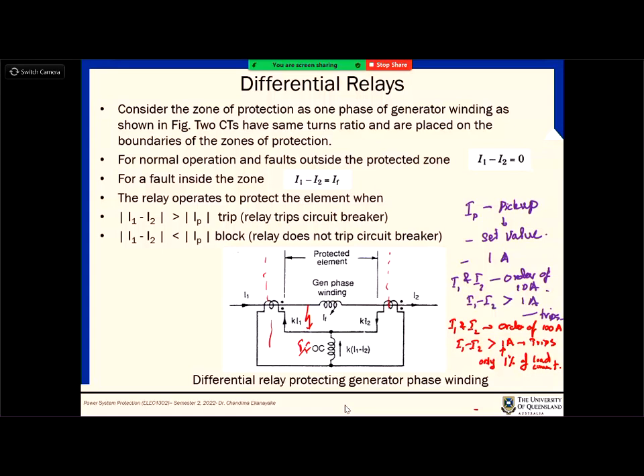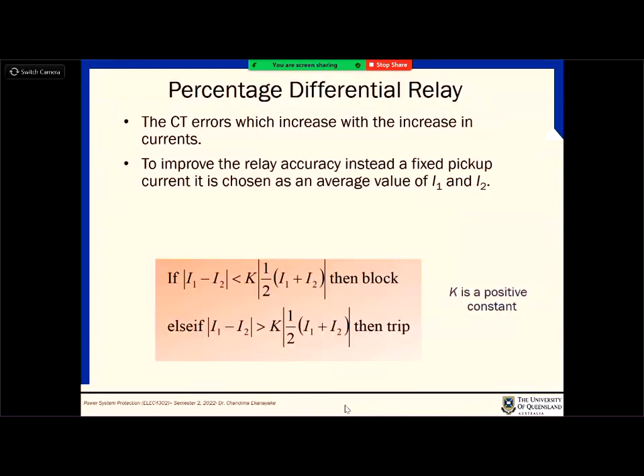As an example, absolute pickup means you take a relay and tell it to operate when, let's say, the differential current is 1 amp, which is the absolute value. So to overcome this issue, we are looking at the same scheme, but it operates in a different way. We identify the pickup in a different way. That is called the percentage differential relay. What does that mean? You can see the conditions here. Earlier, if the current difference was larger than a certain given constant value, then it was tripped. But now, this pickup value is also changing with I1 and I2. That is the average of the two currents.